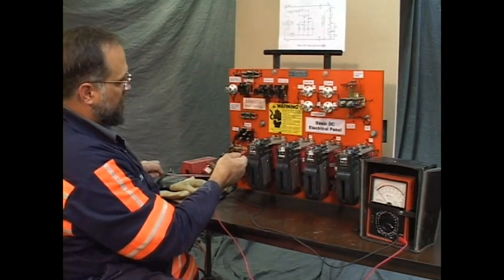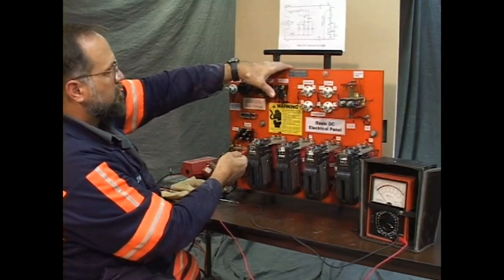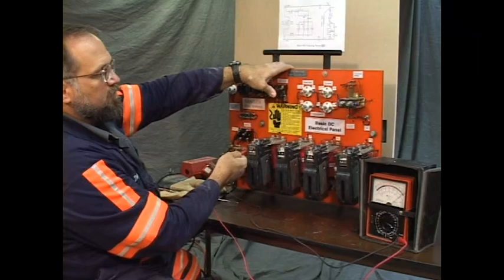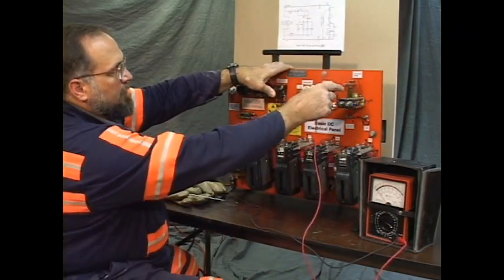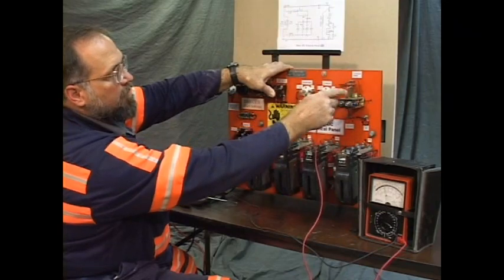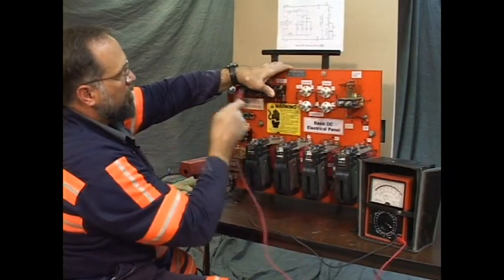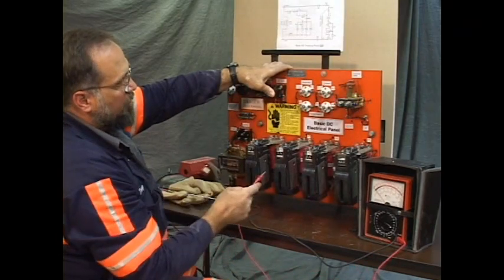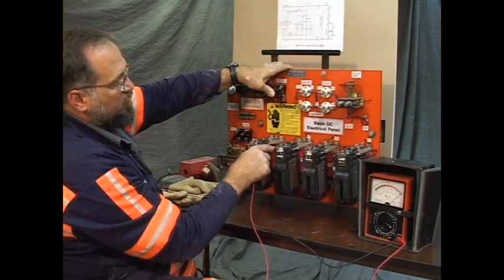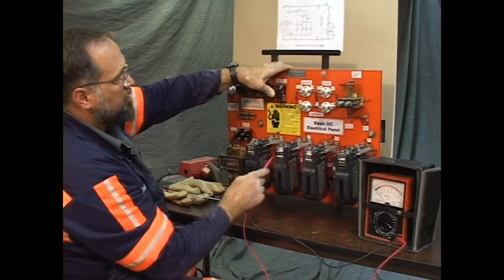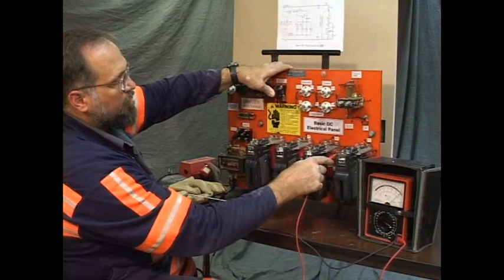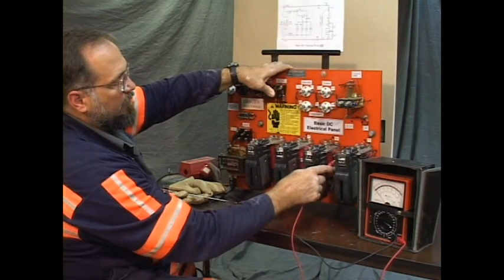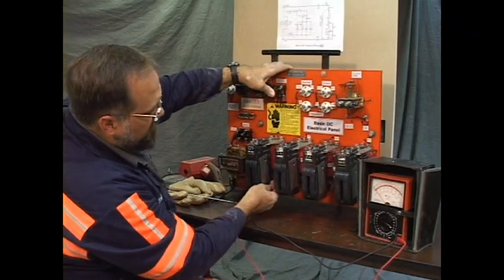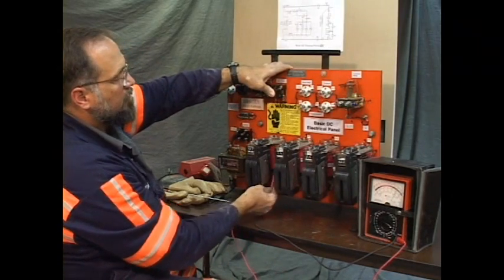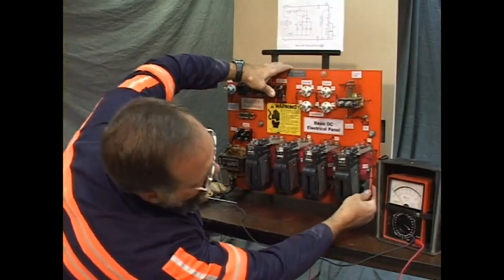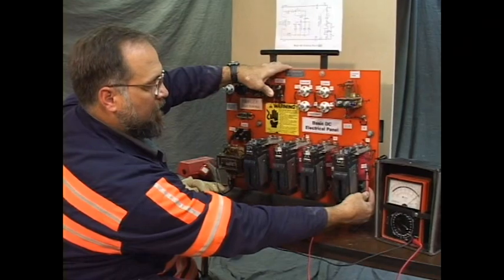Now with that, I'm going to have to lay the probe down and depress the start switch. I'm going to hold that start switch with my thumb, go to the overload relay, the top connection on the mercury tube, and the bottom. From there, I'm going to go with the print: 1A, top of the 1A mercury tube. It should be open. I'm going to check the bottom, and it is. Top of the M2 mercury tube. It should be open. Go to the bottom. It is open. The positive of the M1 starter coil. There we have it. And the positive of the M2 coil. And there we have it.